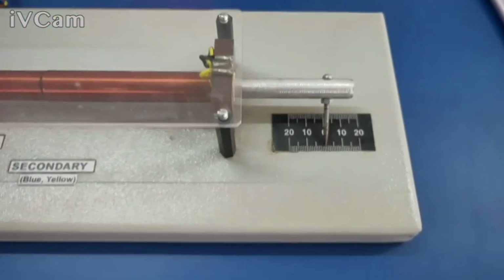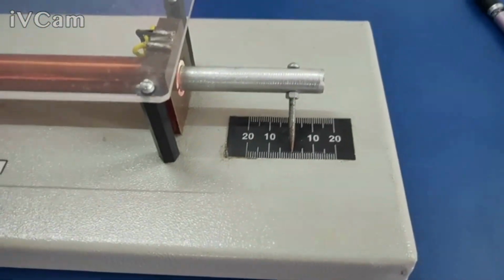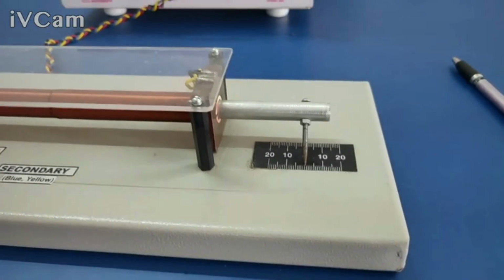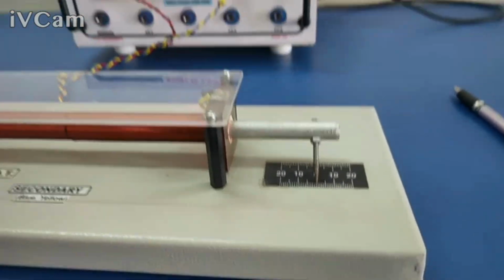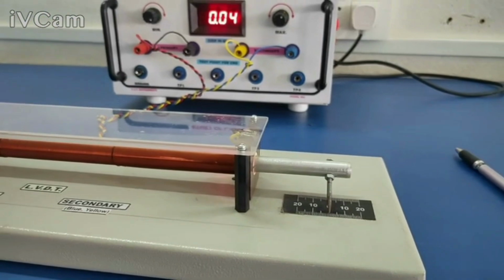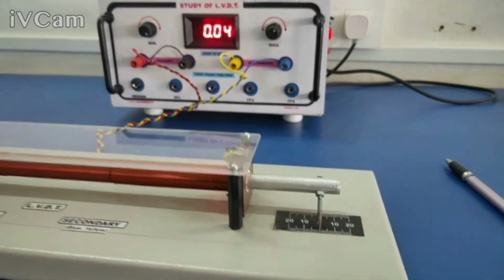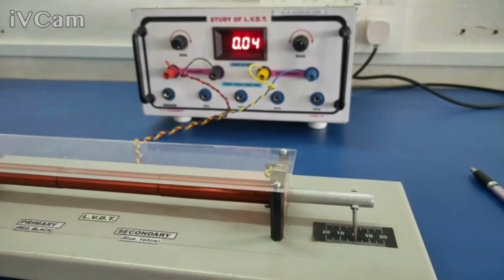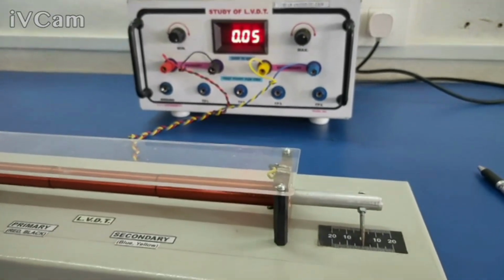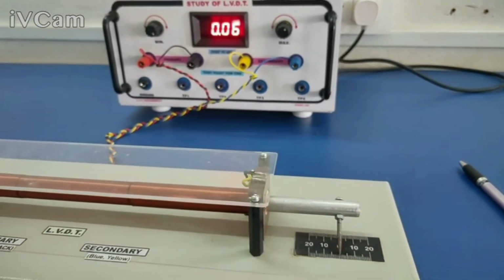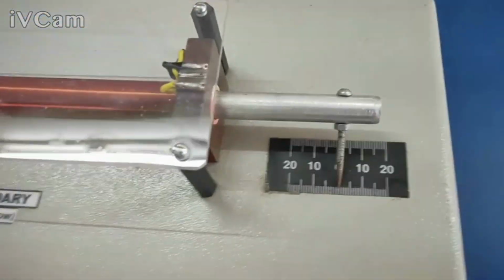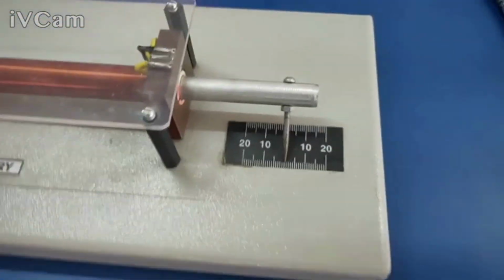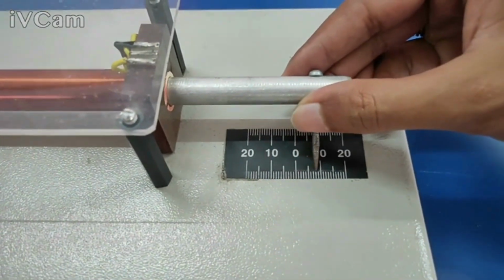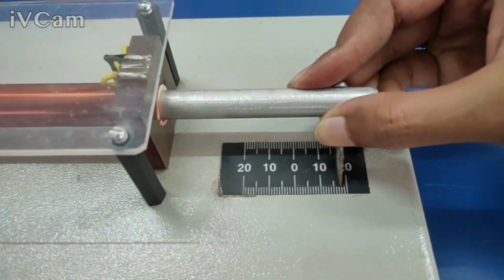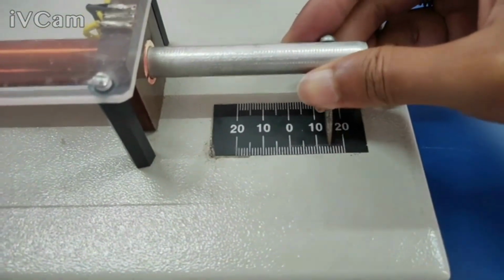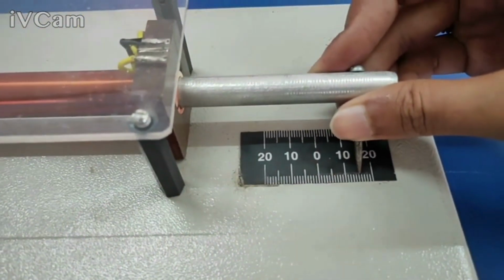So as you see here, again, this is the actual scale. The actual rod core position is at 0 and the DPM reading is slightly 0.04. Now this is what we call a null position calibration. And now we are going to do a similar calibration again at some arbitrary value. Okay. So let us move this core towards the positive side. So what I have done is I have moved the core, I have made the displacement of the core such that now the core is at 15 mm.